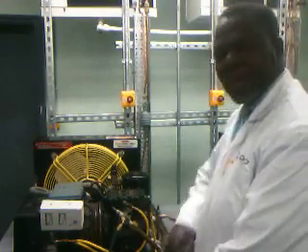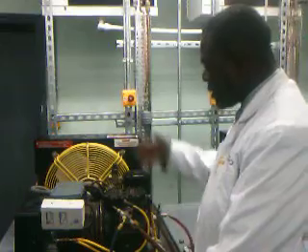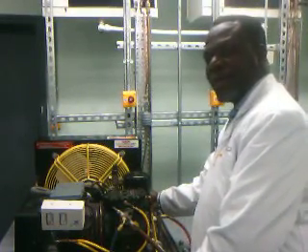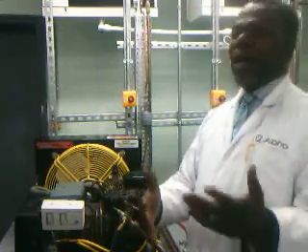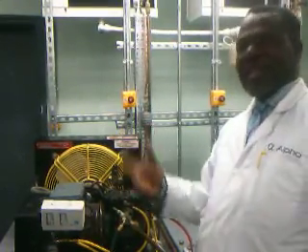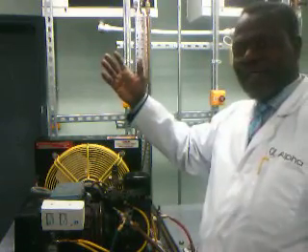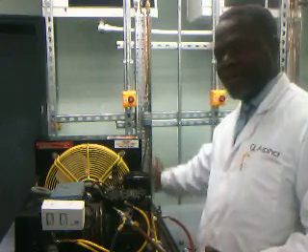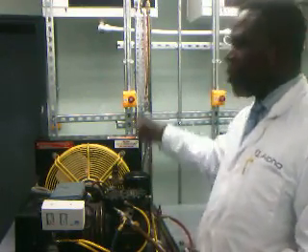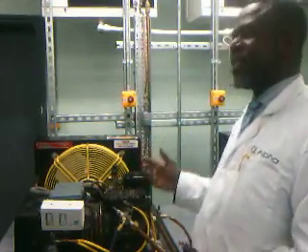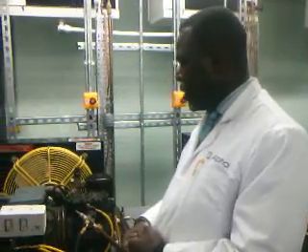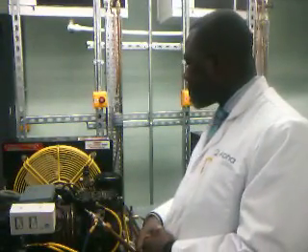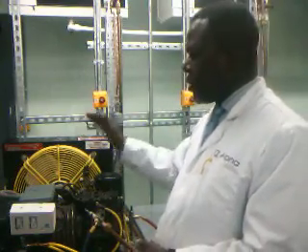If you take the temperature from the high side, which is the condensing temperature, and take a temperature from the outlet of the condenser, and you get, say, 15, or let's say 12, then that means the condensation is too high. The reason could be that there is too much liquid in the condenser, so it's over-condensing. That can affect your system, because you will have too much liquid going into the evaporator, and that can spill over into the compressor from the suction side. So over-condensation is not good. You have to check that.